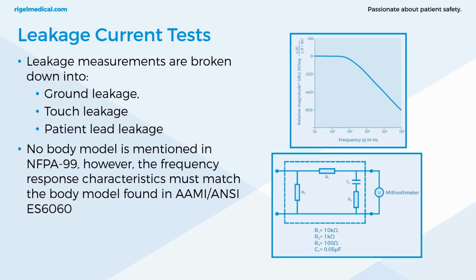So leakage measurements can be broken down into ground leakage, touch leakage, and patient lead leakage. No body model is mentioned in NFPA 99. However, the frequency response characteristics must match the body model found in AAMI ANSI ES, that should be 60601. So to measure those currents, you just need a meter that has frequency characteristics that match this body model on the right.